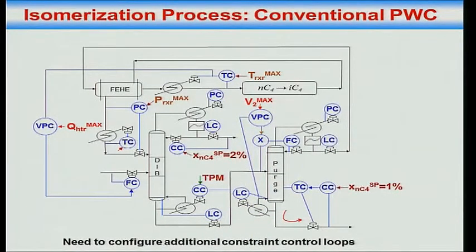But then this boil up approaches max. Once this boil up approaches max, I cannot afford to lose control of what is leaking down the bottoms of this purge column, right? Therefore, what will I do? I will adjust the ratio set point so that this boil up is maintained close to max, but not max, because at max the column will flood. I will probably have to take a shutdown. Yes or no? Alright.